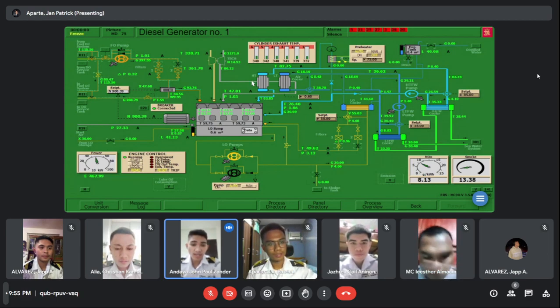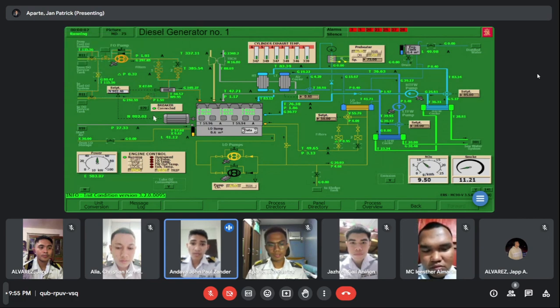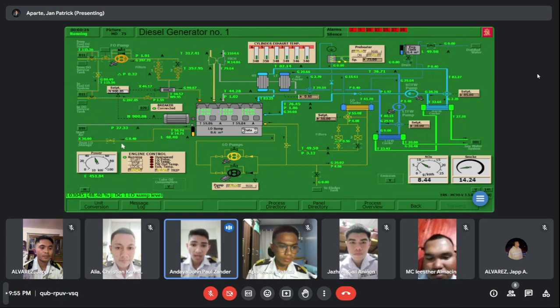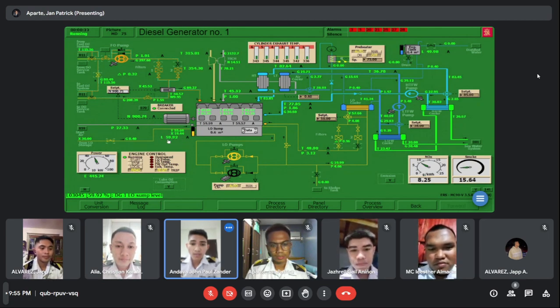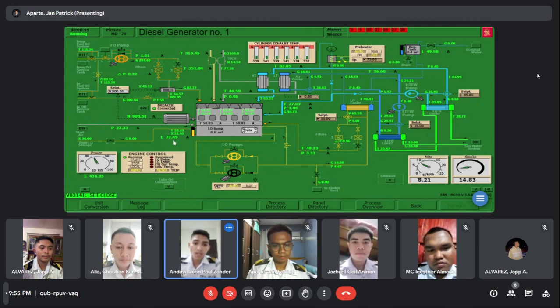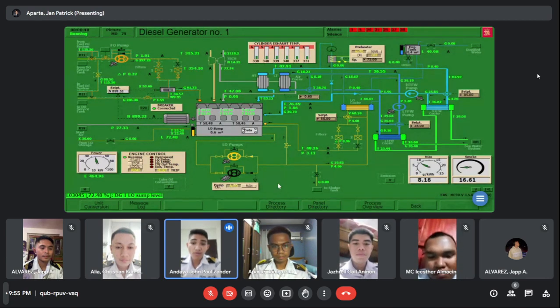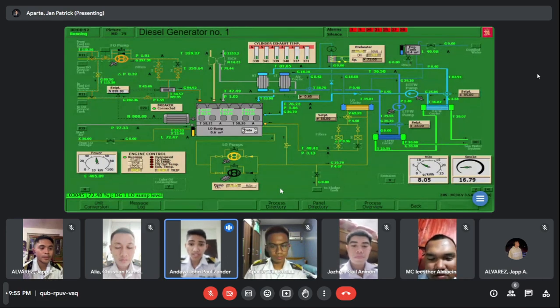Okay, start. Please start. First thing we do is in diesel generator number 1. You can see that the lube oil tank is at low level. We have to fill it up to 70 to 80%. So open the lubrication oil valve to supply, then wait for some seconds to fill it up to 70 to 80%. Just make sure to shut the drain valve of the lubrication oil pump to prevent any alarms. After filling up to the normal level the lubrication oil of DG number 1, let's proceed to DG number 2.